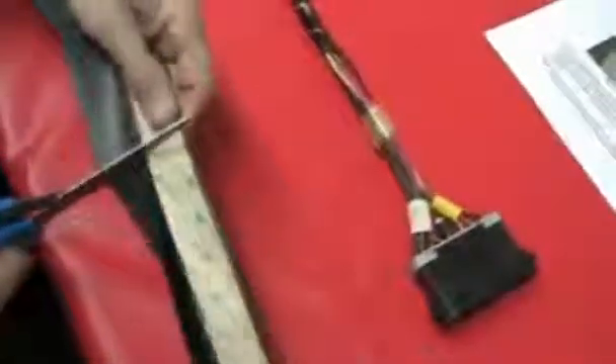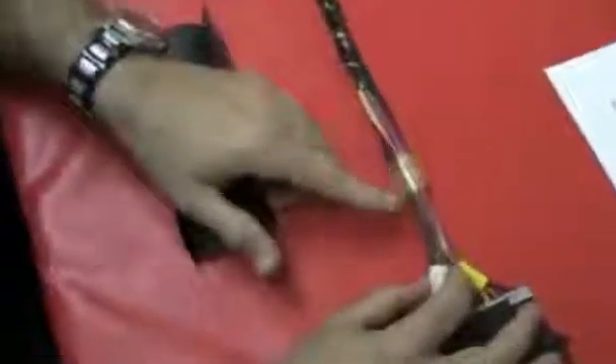Now, because this cable is short, I'll just cut a short piece of the tubing. Again, the big advantage of doing this is when you're done, this area will be water blocked, no moisture will go on up the cable. But the rest of the cable will remain somewhat flexible.